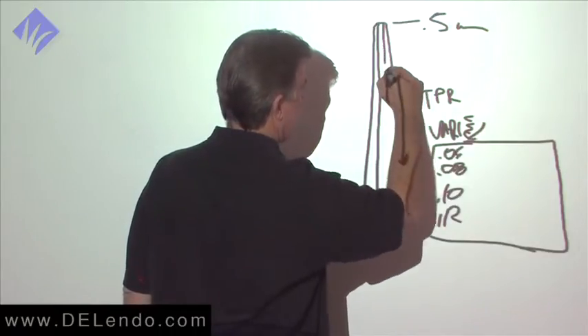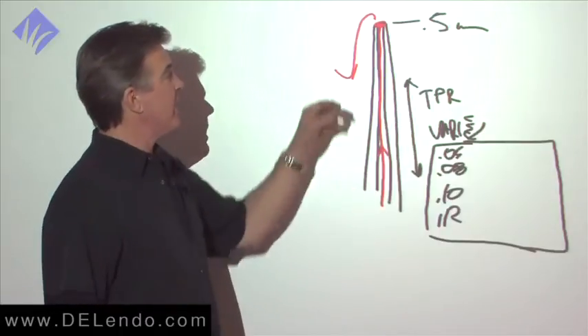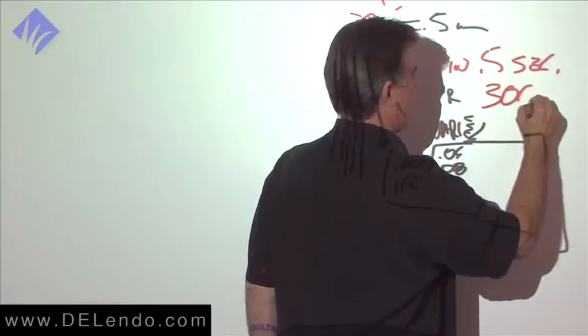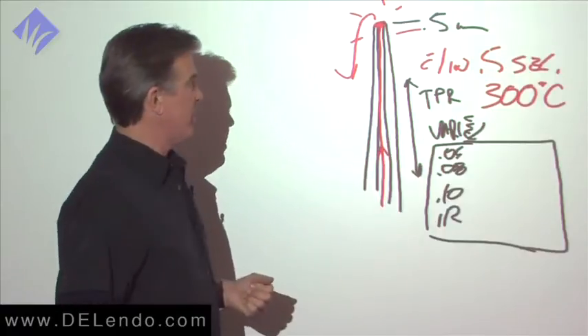The clever thing is these are basically hollow stainless steel tubes. Inside that is an insulated copper wire through which electric current goes up to the tip. There's a little solder joint here, and the ground is this direction. This is stainless steel. It's resistant to electric current, and that's why heat flares at the very tip of the plugger within 0.5 seconds. We have a spike of 300 degrees C at the tip of the instrument. This has a feedback system so that we can track that.